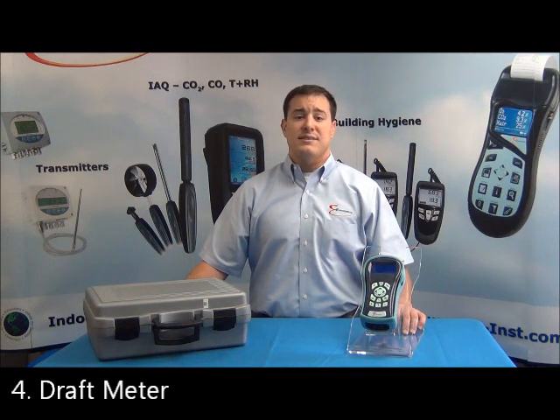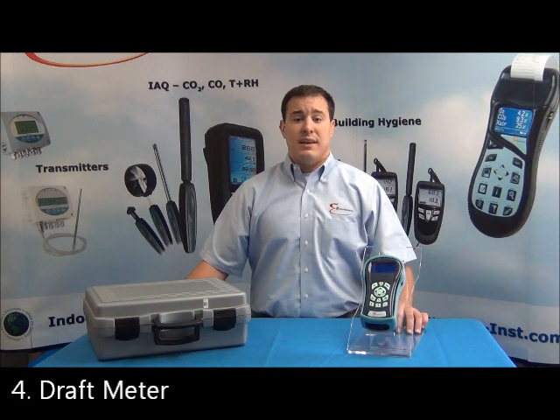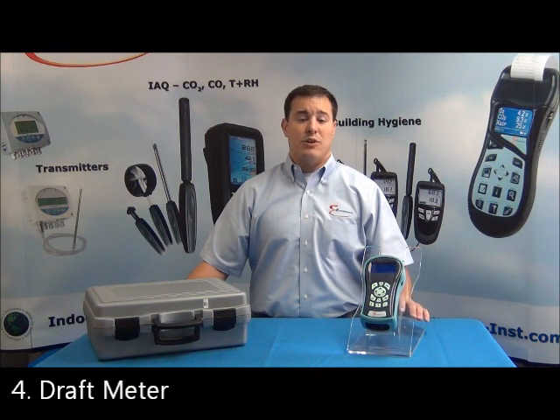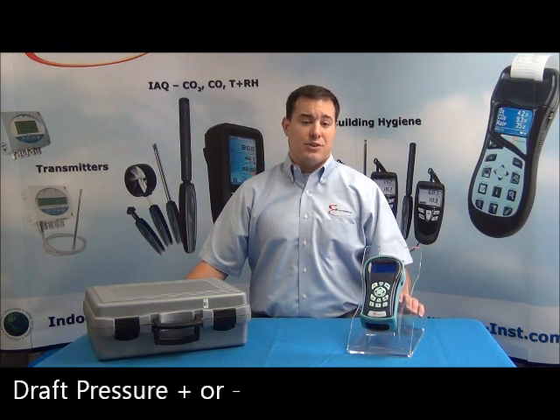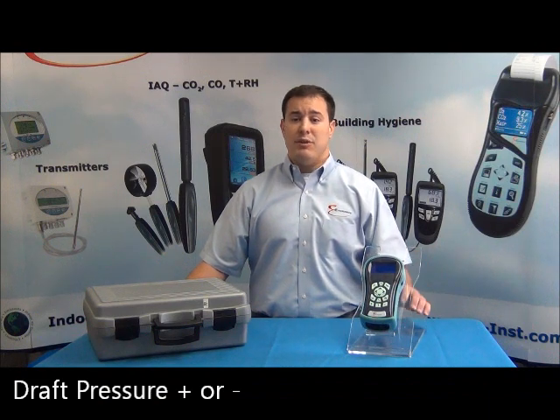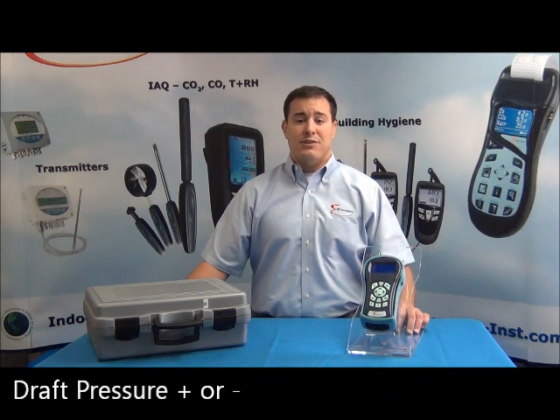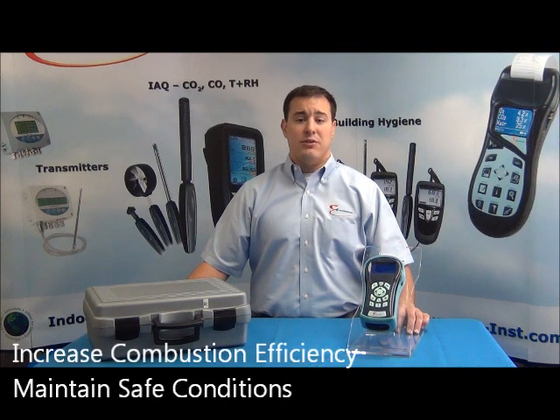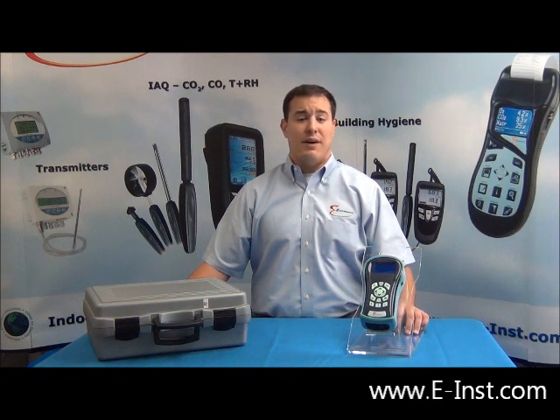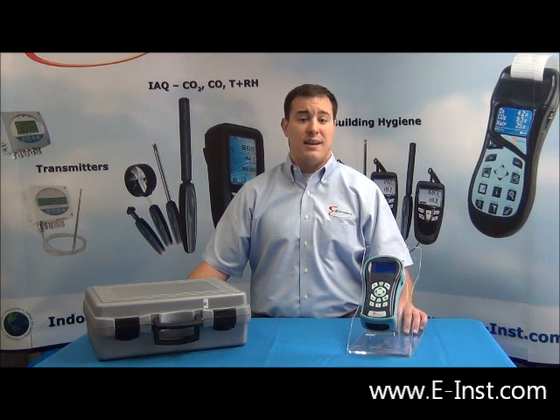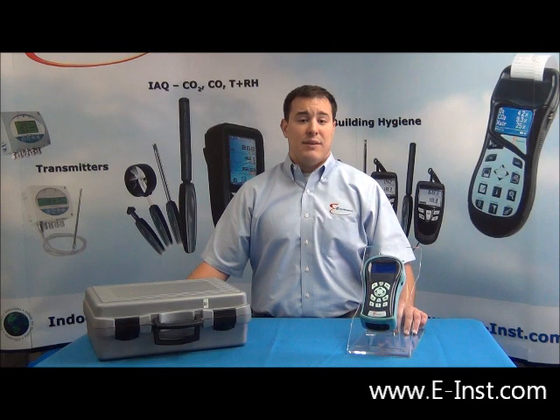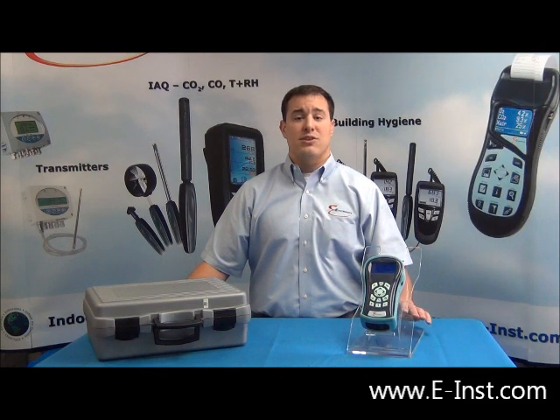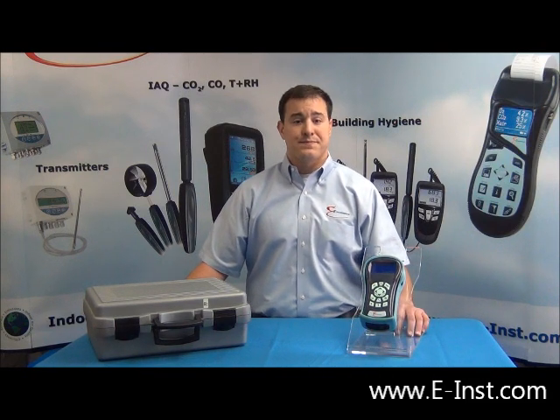The pressure of the gases in the stack must be carefully controlled to ensure that all of the gases in the combustion zone are removed at the correct rate. This draft pressure can be either positive or negative depending on the boiler design. Monitoring this draft is important not only to increase the combustion efficiency, but also to maintain safe conditions. Low draft pressures create buildups of highly toxic gases such as carbon monoxide and explosive gases. If you're not testing for draft, you are doing a disservice to the equipment and the customer.